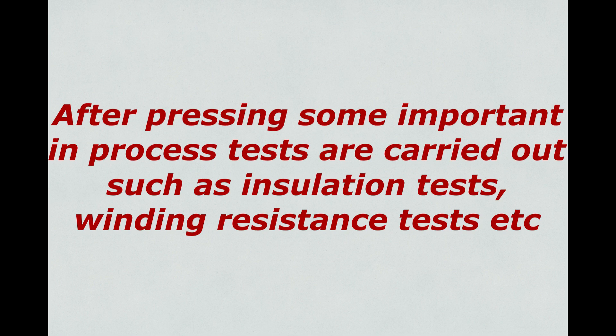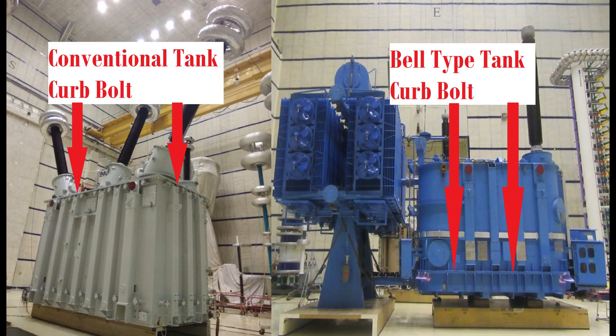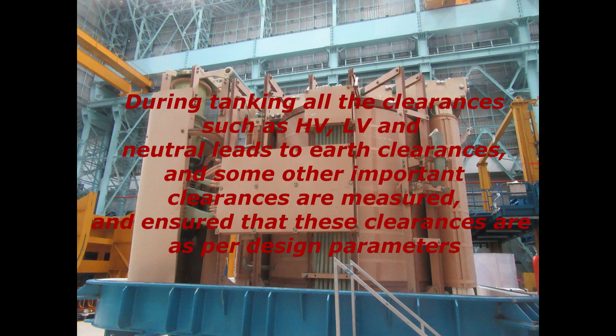After pressing, some important in-process tests are carried out such as insulation tests and winding resistance tests. Stage 6: Tanking. Post pressing, tanking preparations are done. There are mainly two types of tanks: conventional tank and Bell Type Tank. In a conventional tank, curb bolts are at the top; in a Bell Type Tank, curb bolts are at the bottom. During tanking, all clearances such as HV, LV and neutral leads to earth clearances and other important clearances are measured and ensured to be as per design parameters.